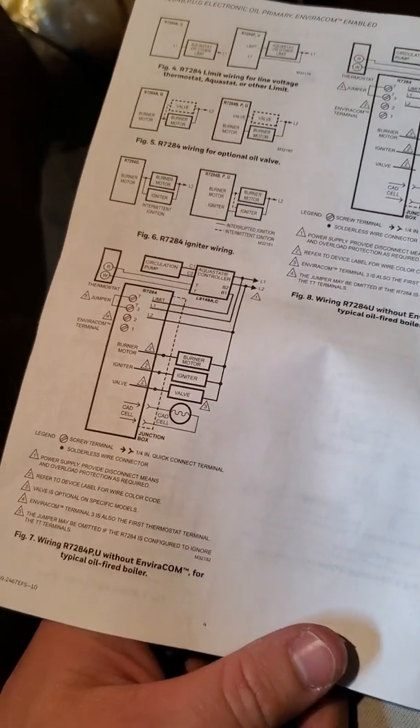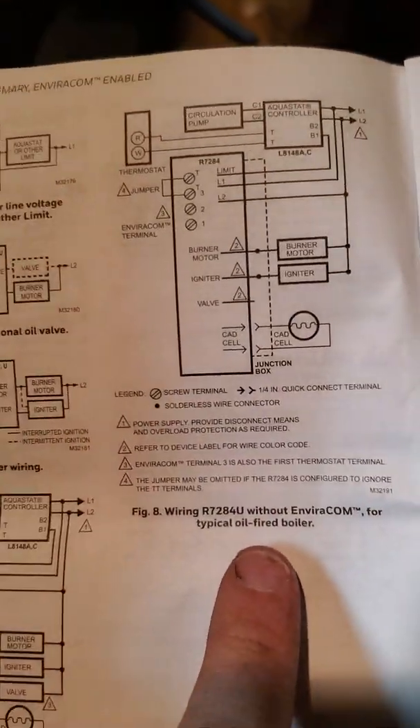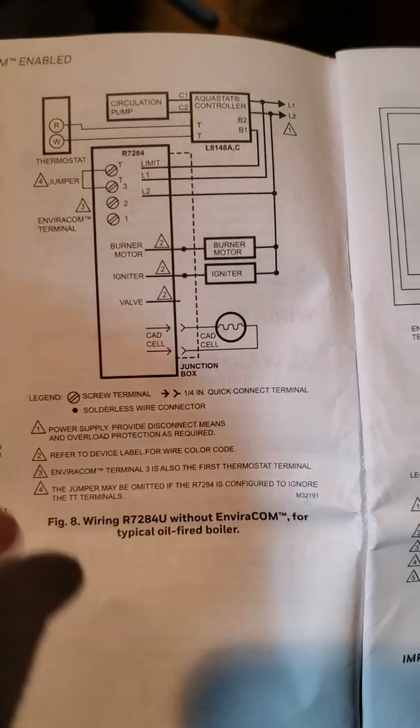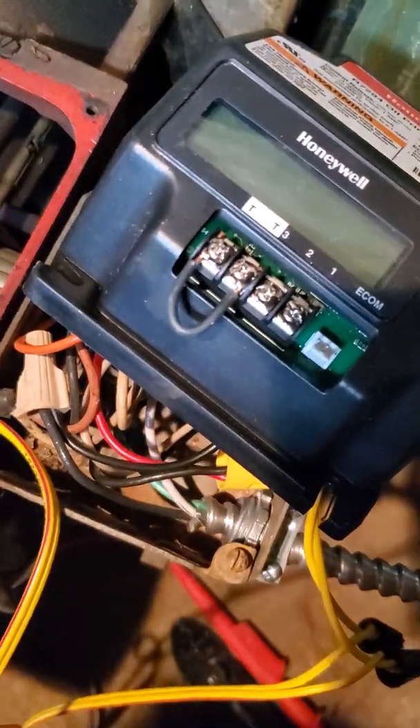This is more or less an overview, but you have all these different scenarios. Because I have a boiler and we're not using this - what do they have? This EnviraCOM, and I imagine that's that Ecom port right there. Since I don't have an EnviraCOM and I do have an oil-fired boiler, here's the CAD cell that I replaced at first. It seems I had a problem with the brain, so you want to put your jumper in from T to T, and there's your guy right there.